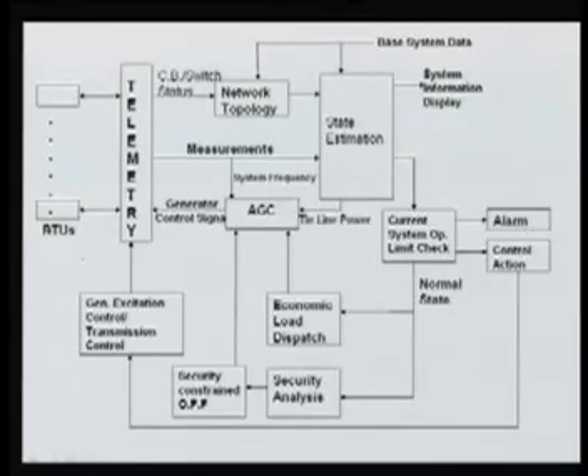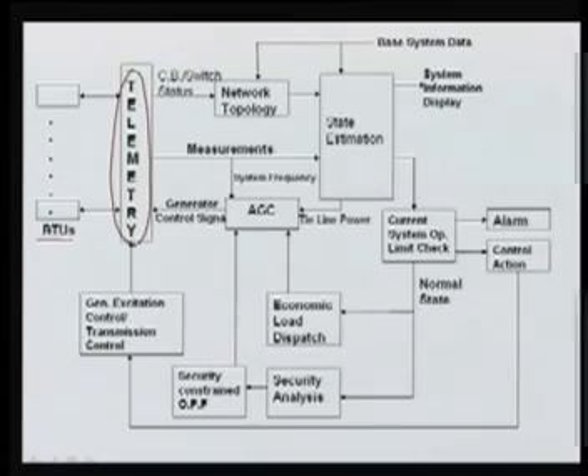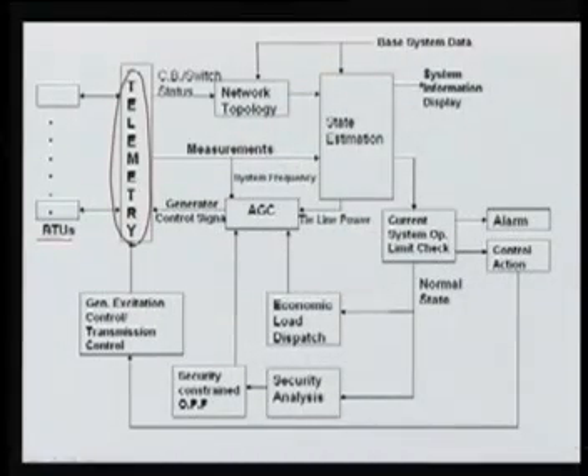Here is a block diagram of the various functions of modern energy management systems. First, we start with the RTUs. RTUs are nothing but remote terminal units, by which we measure the power system data from the field, and this RTU gives information to these various modules through telemetry. The RTUs are large in number in the power system. They are spread all over the world, and they give the various measurements and the circuit breaker and switch status, and with this information we do various other functions, like forming the network topology here.